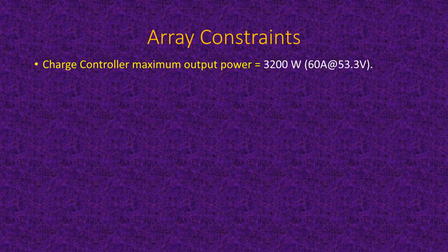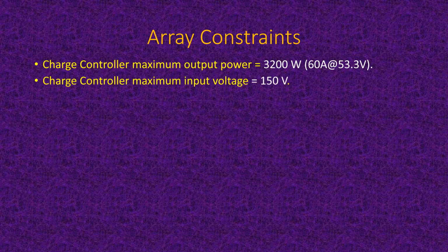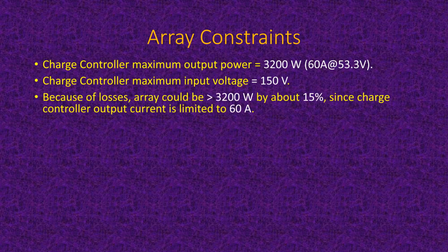Let's look at some constraints on the array. With this particular system, you can't do more than 3,200 watts at the output of the charge controller for a particular 60 amp charge controller. That doesn't mean you can't use two charge controllers, but if you have only one, maximum input voltage of 150 volts. And so the array could actually be more than 3,200 watts by about 15%, and you're still okay, because the charge controller output current is limited to 60 amps.